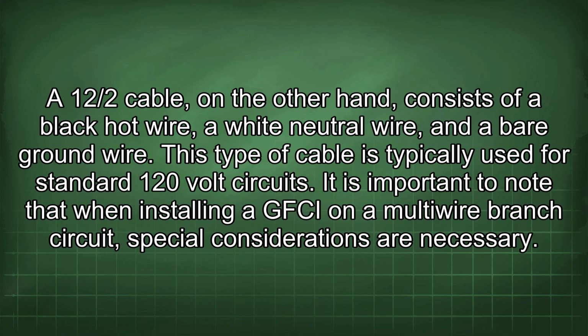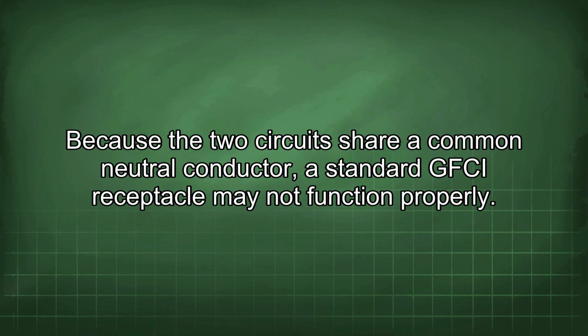A 12/2 cable, on the other hand, consists of a black hot wire, a white neutral wire, and a bare ground wire. This type of cable is typically used for standard 120 volt circuits. It is important to note that when installing a GFCI on a multi-wire branch circuit, special considerations are necessary. Because the two circuits share a common neutral conductor, a standard GFCI receptacle may not function properly.